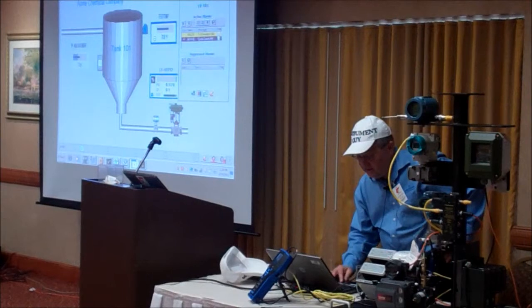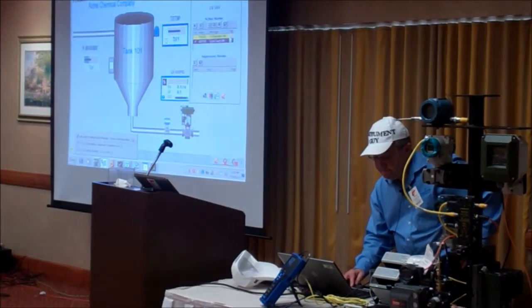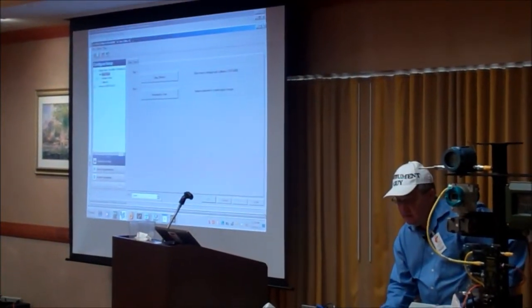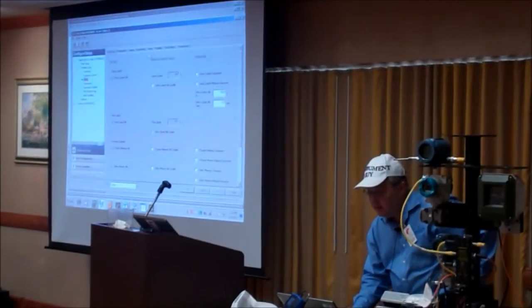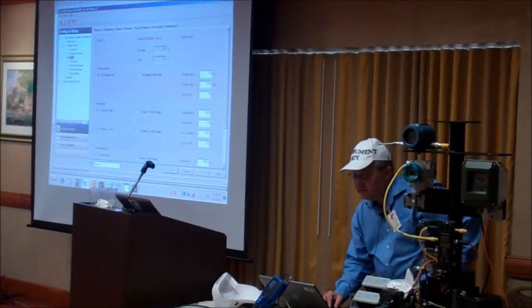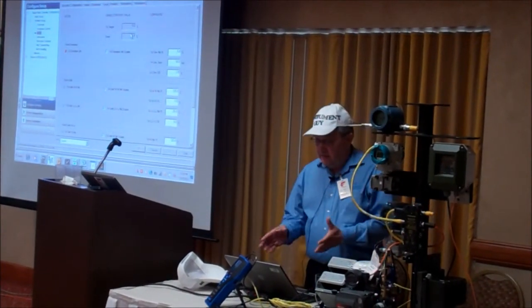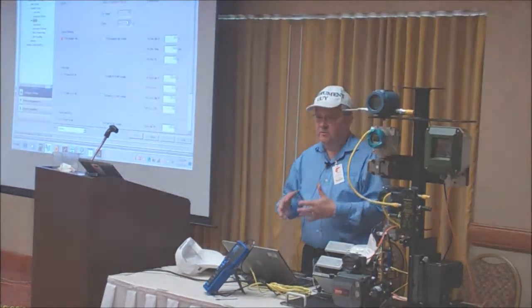The instrument guy calls that up and says, I'm seeing the same thing here. I'm seeing a travel deviation. I'll take a look at that. And got travel deviation alert. Oh, looky here, the target's 15%, but it's stuck at 41%. So something's going on there. So this is something the operator wants to know about. This is something that's probably got to be fixed right away. So we needed to alert him.